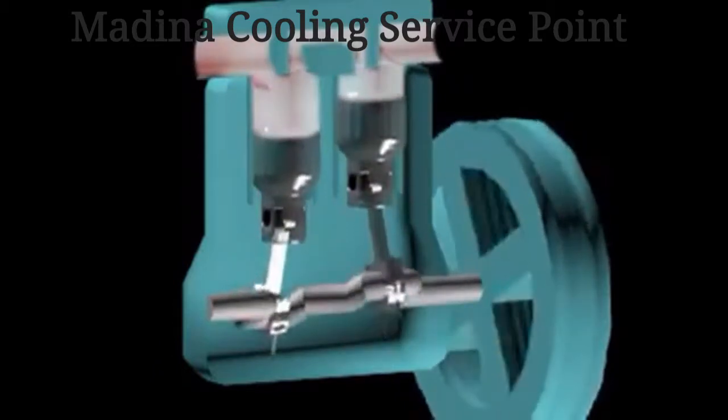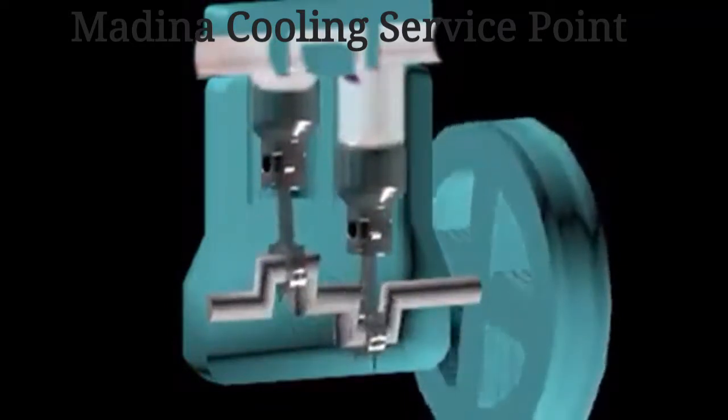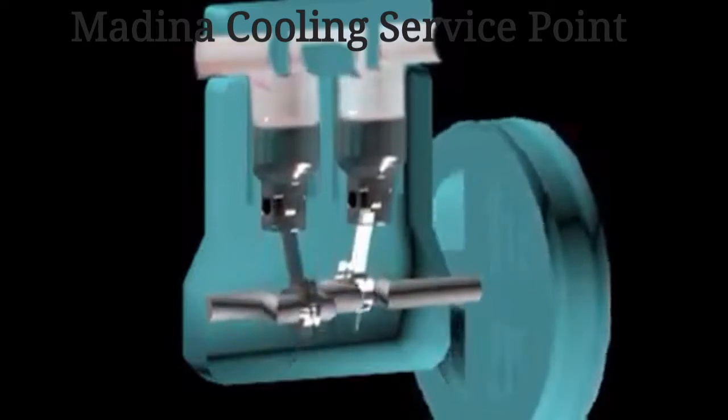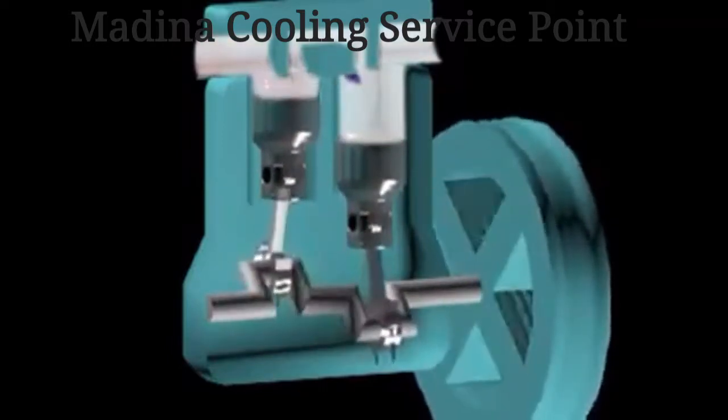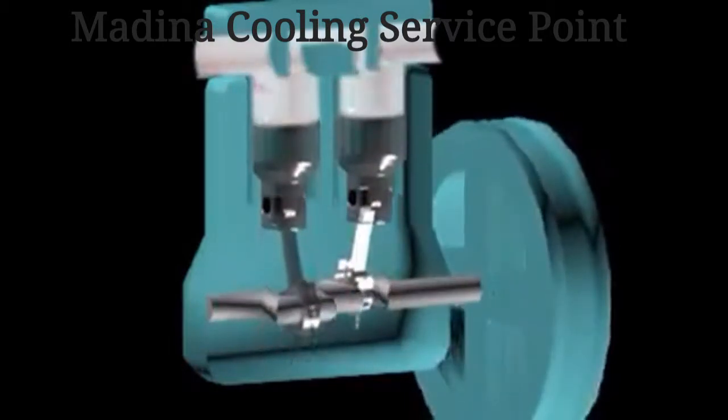On the suction stroke, where a piston is moving downward, the clearance space between the piston and the cylinder head will expand. The drop of the pressure will open the plate-type suction valve and force the refrigerant to enter the chamber until such time as the suction valve recedes.